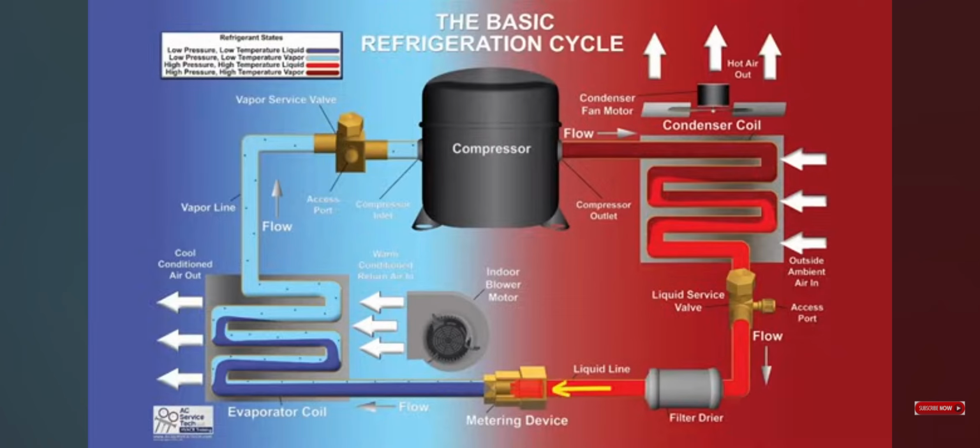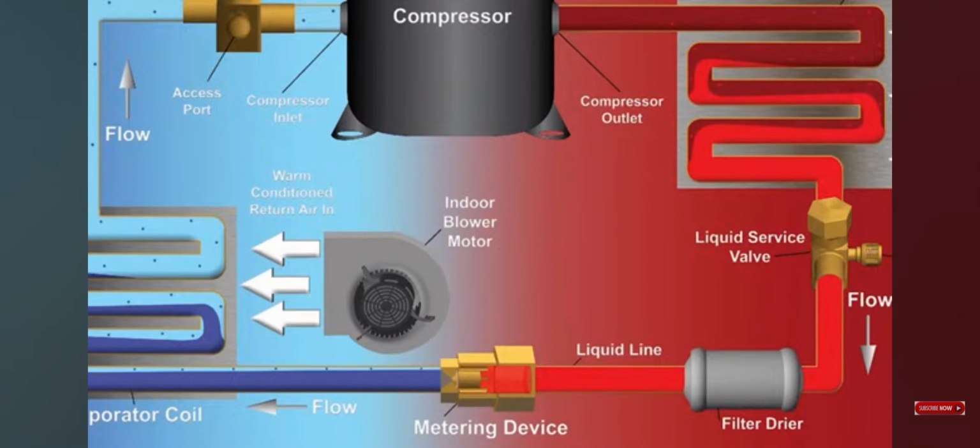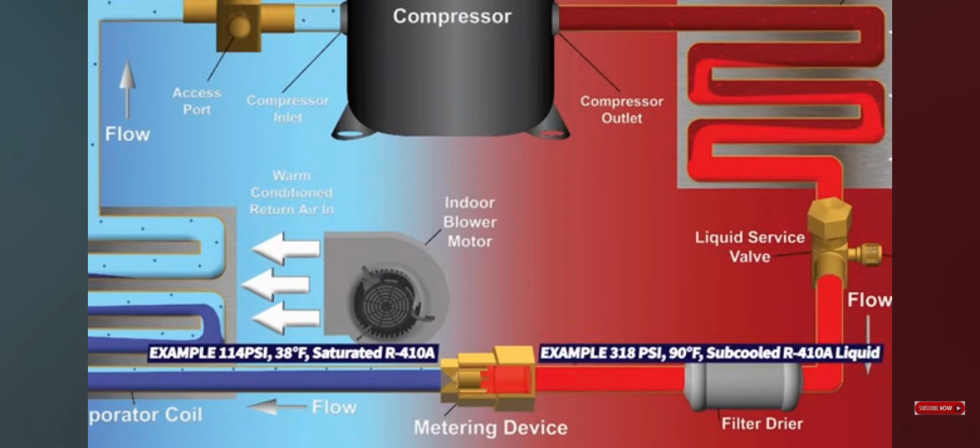So then you have the refrigerant entering into the metering device. So it's a high pressure, high temperature, subcooled liquid refrigerant entering. The refrigerant is forced to go into the inside of the piston metering device, and then it's going to lower in pressure. So then it's going to be in the low pressure liquid state. But really, as you can see, there's a little bit of light blue at the top. That is your little bit of vapor refrigerant. So what's happening is you're reducing the pressure so much that the refrigerant has a chance to expand. And so you have 80% liquid, 20% flash gas.